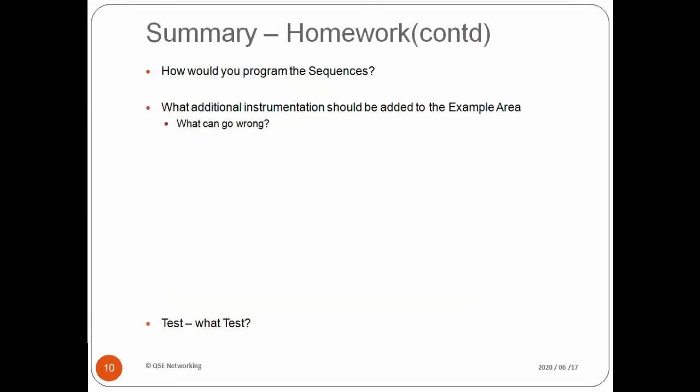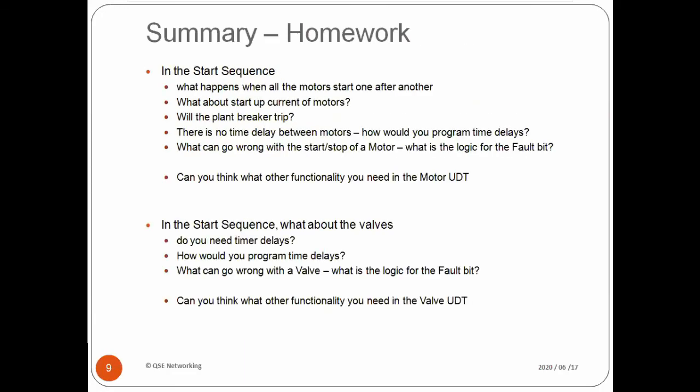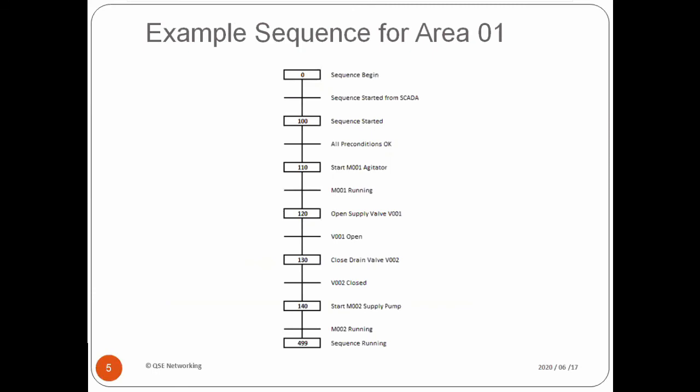Right, just how would you program the sequence? You can see, if I just go back to our sequence, that sequence is drawn like there's a programming language called GraphSet or SFC, sequence flow chart. If you program GraphSet in the Siemens, you need to load another package, which costs money, but that's beside the point. There are a lot of PLCs with GraphSet or SFC built in.